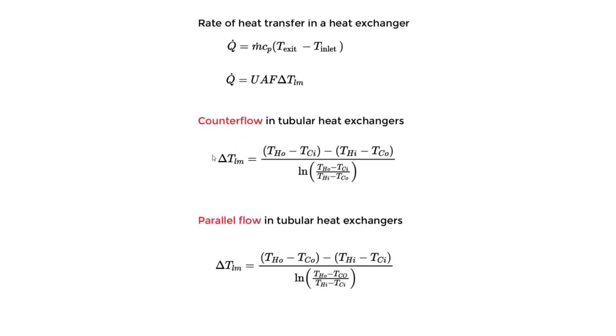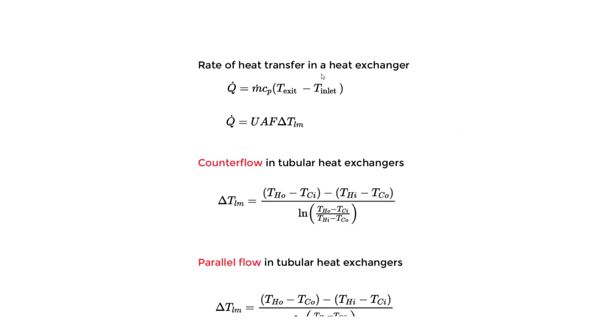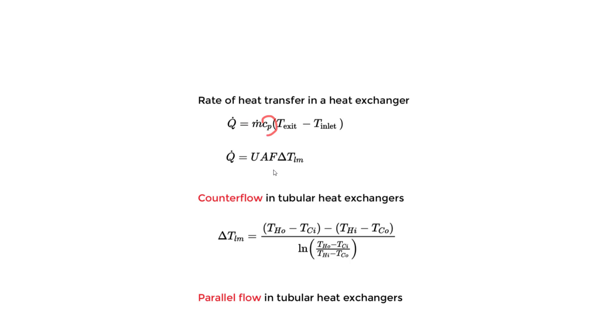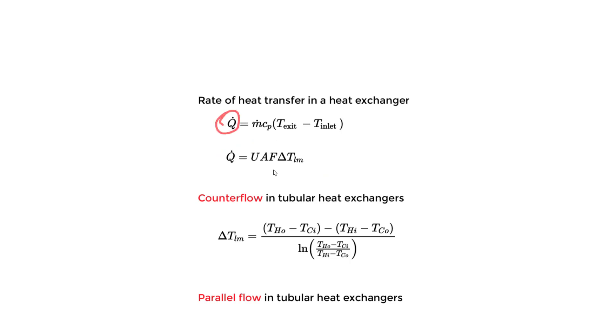Using equations from the handbook: the rate of heat transfer in a heat exchanger is Q dot = M dot × CP × (T_exit − T_inlet). There is also another equation for heat transfer rate involving the area: Q dot = U × A × F × ΔT_LM. We'll find Q for water using the first equation, then plug it into the second equation to find the area. F will be assumed to be 1.